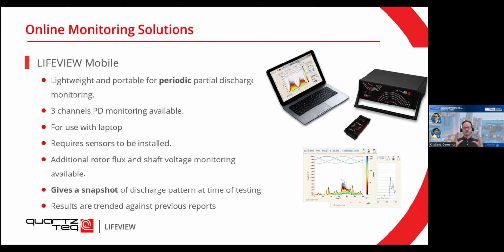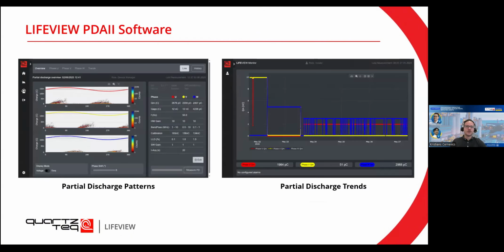So instead of the continuous monitoring that gives you data every few hours, this will give you a snapshot of a discharge pattern at the time of testing. So then depending on how often you do these measurements, you're going to have a history of the discharges. And the results are essentially trended against previous reports, like I showed you in this real case situation. All of these solutions come together with an analysis software. So first of all, this software is going to show you the partial discharge patterns on the left side, and then also the trends on the right side.